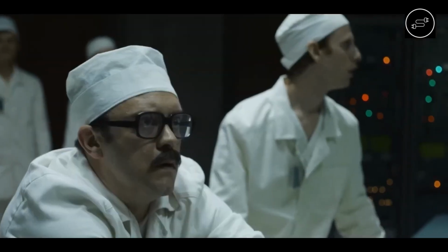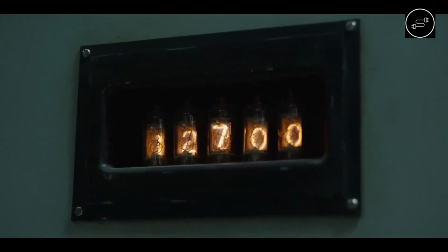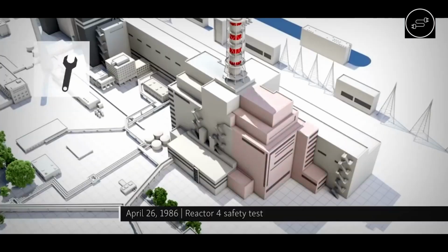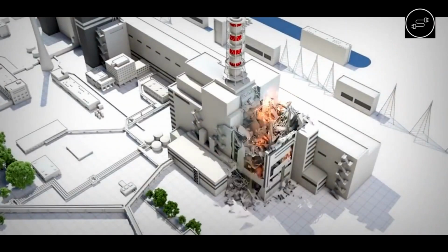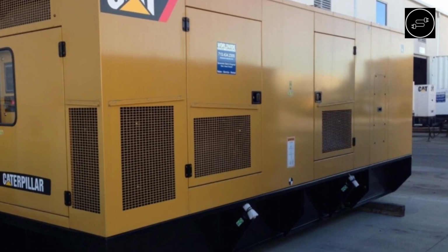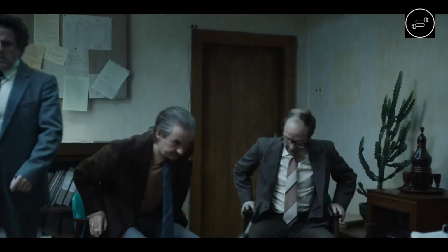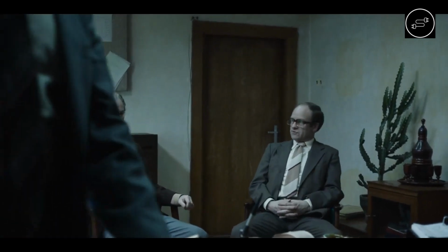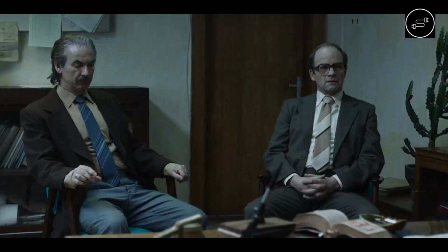The disaster was a result of multiple failures, both human and technical. The incident occurred during a safety test designed to determine whether the slowing turbine could generate enough power to keep the reactor's cooling water pumps running in case of a power outage before the backup diesel generators kicked in. A similar test had been conducted the previous year, but the results were unsatisfactory due to a rapid drop in turbine power. This time, new voltage regulators were introduced to improve performance.